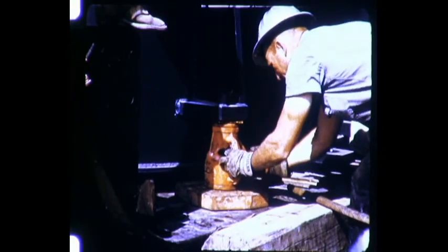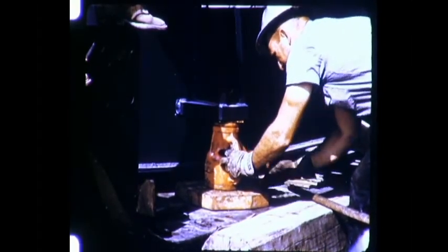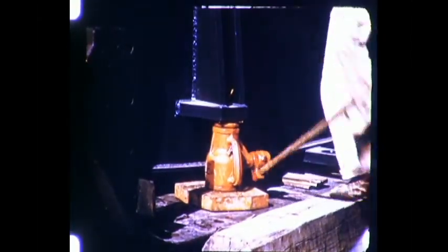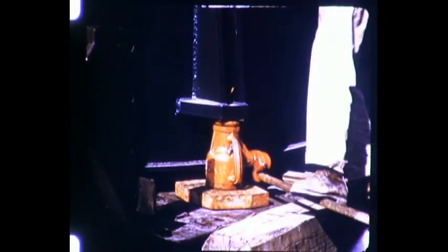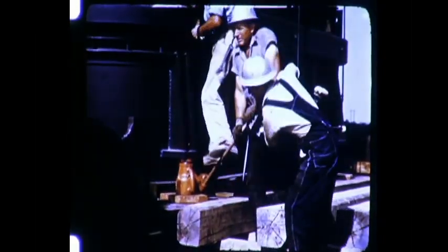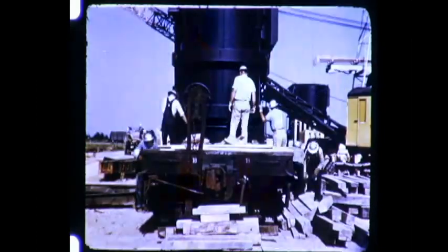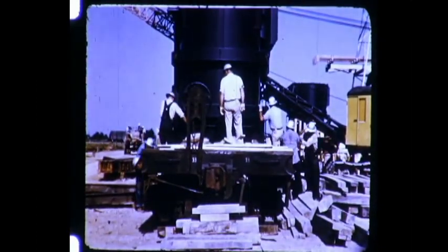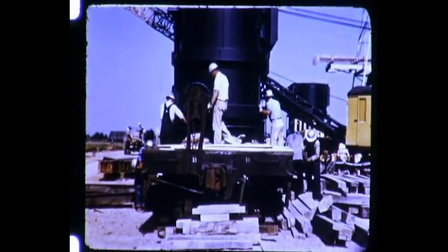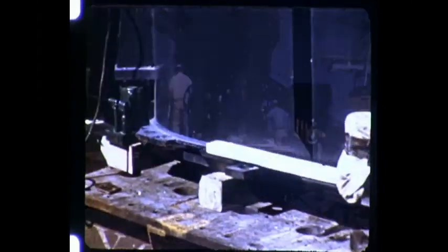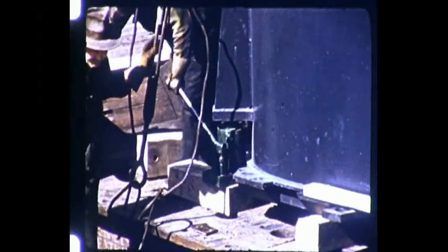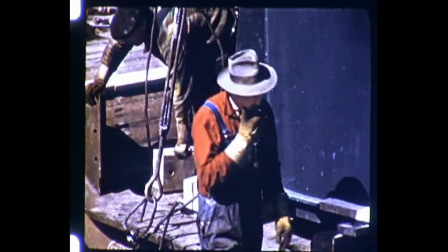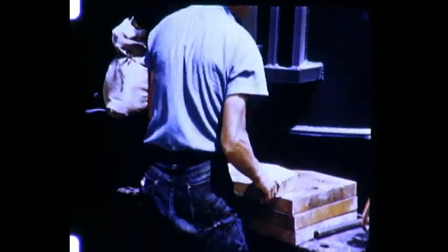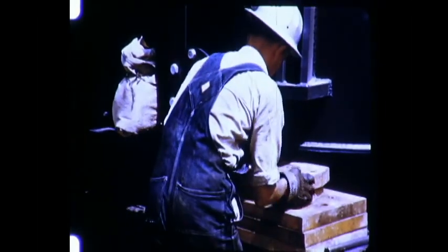With the cribbing in place, we're ready to start jacking the transformer. 50-ton mechanical jacks are placed under the convenient jack bosses. And the job here is to raise the unit slightly above the level of the footings. 2 corners are jacked simultaneously at one end of the unit, and with timbers placed under the base to hold the gain in height, the jacking process is repeated at the other end of the unit. As the transformer moves up, blocks inserted under the jacks provide a higher base for further jacking.